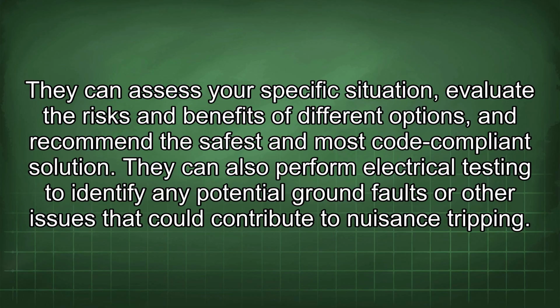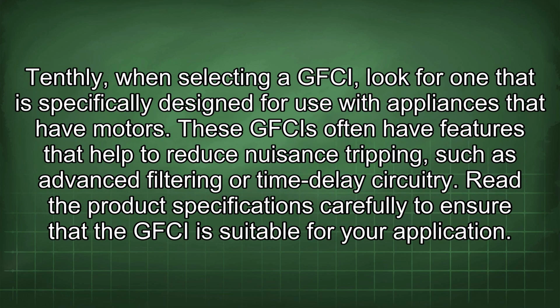They can also perform electrical testing to identify any potential ground faults or other issues that could contribute to nuisance tripping. Tenthly, when selecting a GFCI, look for one that is specifically designed for use with appliances that have motors. These GFCIs often have features that help to reduce nuisance tripping, such as advanced filtering or time delay circuitry. Read the product specifications carefully to ensure that the GFCI is suitable for your application.